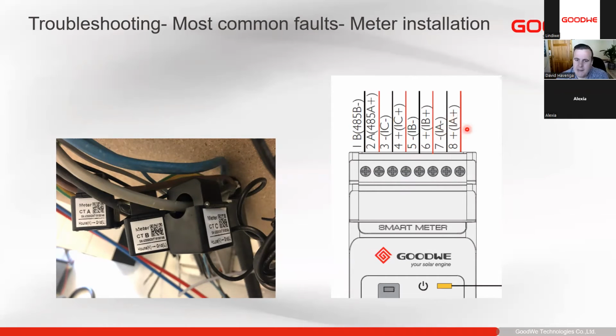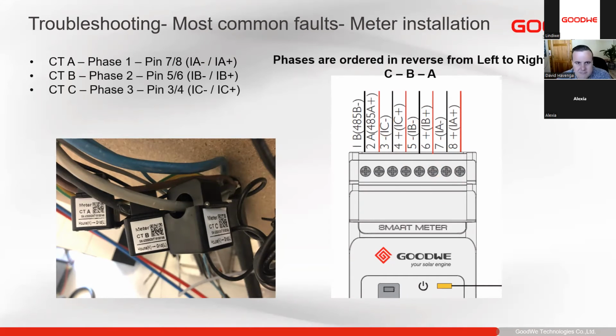Please also notice here, A is 7 and 8, B is 5 and 6, C is 3 and 4. So phase 1, phase 2, phase 3. This is from right to left. So please, the wiring is on the side of the smart meter as well as the user manual of the inverter and the user manuals of the smart meters, which can be found on our website. So if you have to remove these cables to route them into a different box, please pay very careful attention to that to make sure you connect them correctly, because this incorrect connection is a nightmare for fault finding. So as you'll see, CBA. So it's reversed.